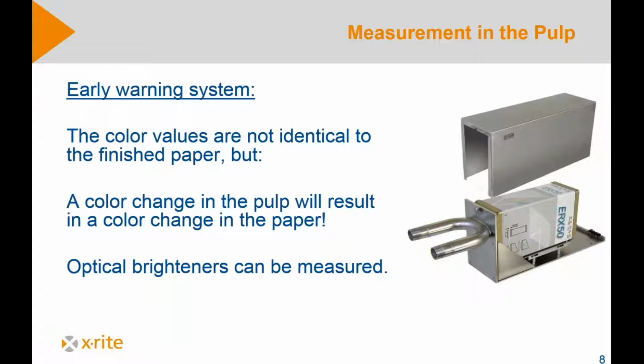How does the system look like? Basically, it's our ERX50 instrument, which is built in a box. And we have a U-tube over here where the pulp goes through. It has a special design so that the pulp does not stick on a window. There is a glass window where we measure through. So this is a very easy to build in system because we have just a small bypass, approximately a 1 inch tube where you can measure the pulp.